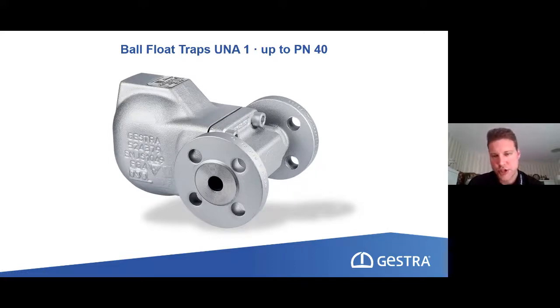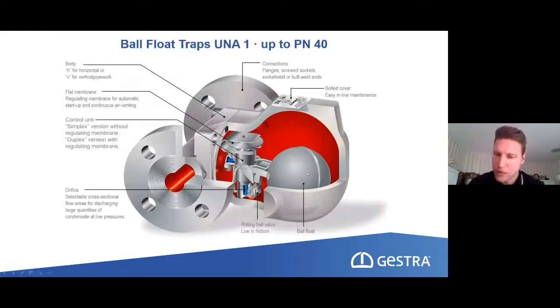So we had to change some things, and we created the so-called UNA 1, which is a ball float steam trap, but the design is a little bit more simple. So we have here the advantages of a ball float steam trap. If we take a look inside, we have the ball float and the rolling ball valve here at the outlet of the control unit to the condensate line. And then we have here a conic connection, and then we press the control unit onto this conic connection, and then we have a fully functional ball float steam trap with all its advantages, because we also can attach an air venting membrane here above.